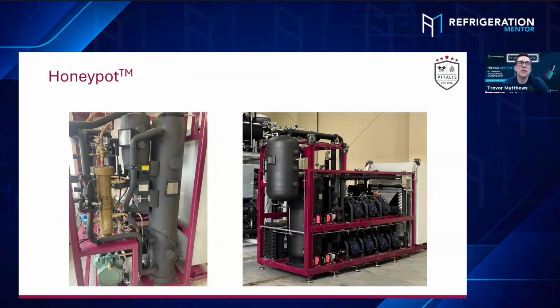What is your strategy? On a startup, if you're going out and doing a startup, the systems are dry. I'm assuming there's no oil in any of the compressors or anything like that. What is your strategy after they get 150 psi or 10 bar in there of vapor? How do you recommend they add the oil as well as test the oil components?